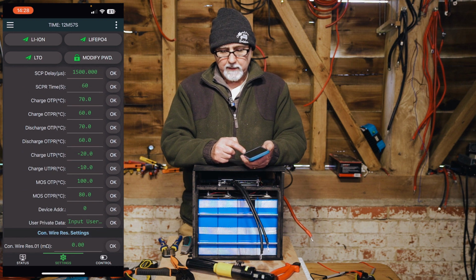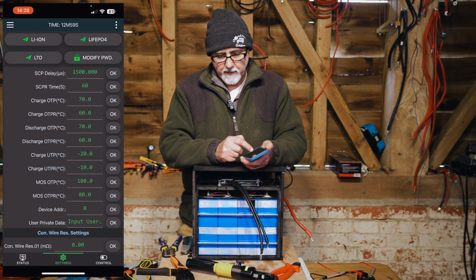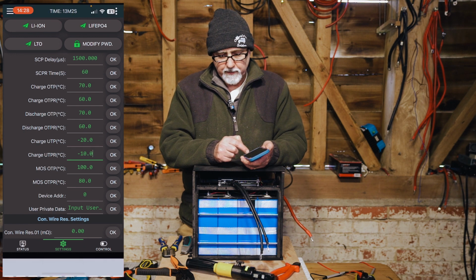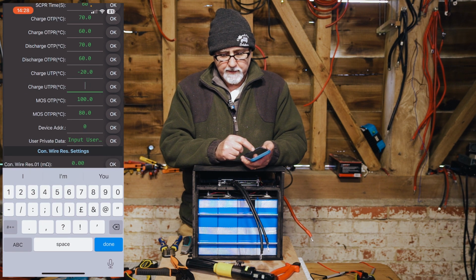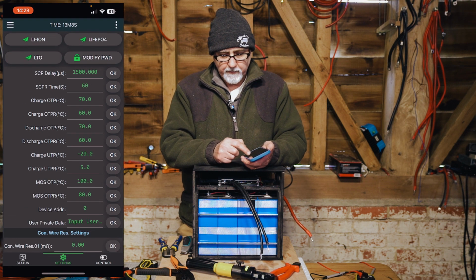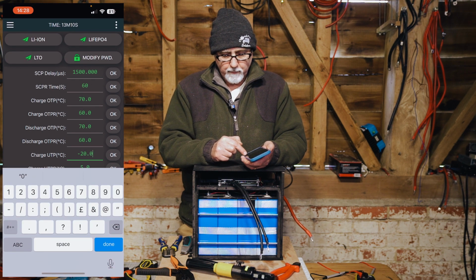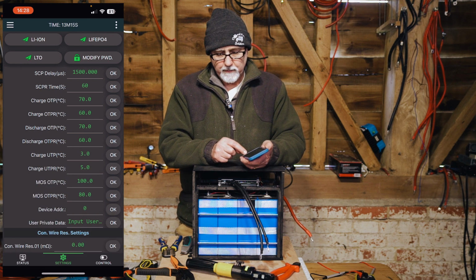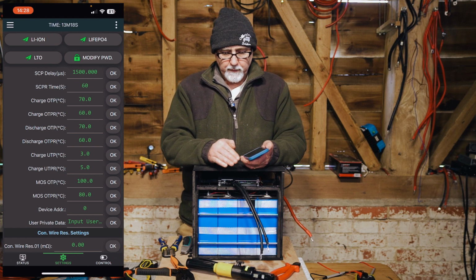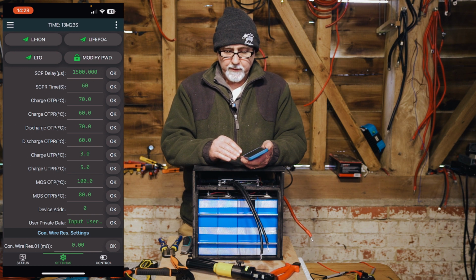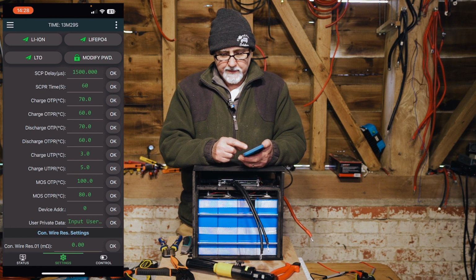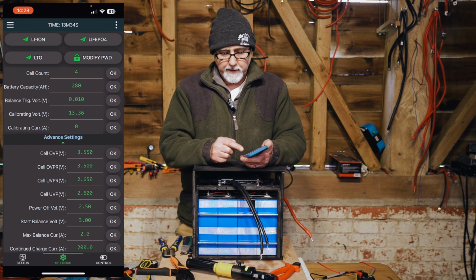There are two final parameters to change: the under temperature protect reset, which we'll set to 5 degrees centigrade, and the under temperature protect, which we'll set to 3 degrees centigrade. So when the cells drop to 3 degrees, it will stop allowing charge until the temperature rises back to 5 degrees. Those are all the settings we want to change from default.